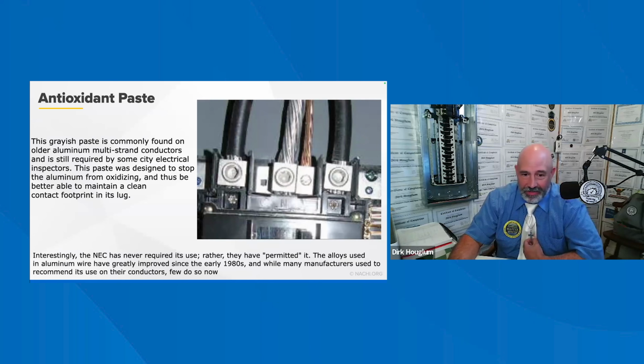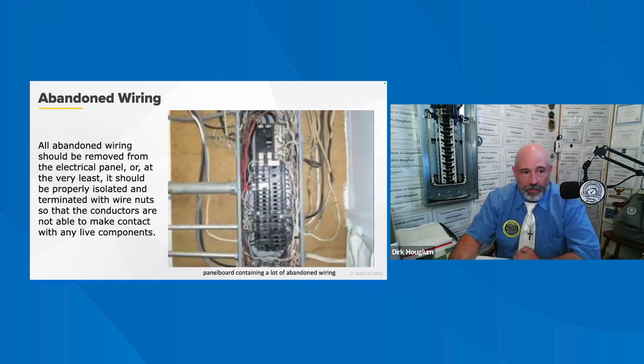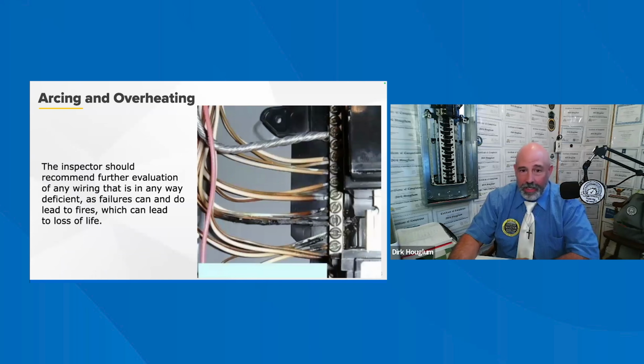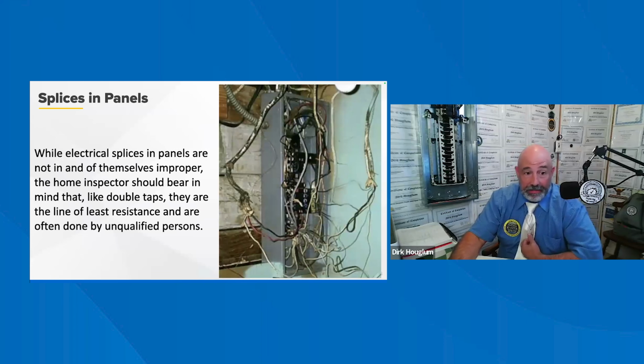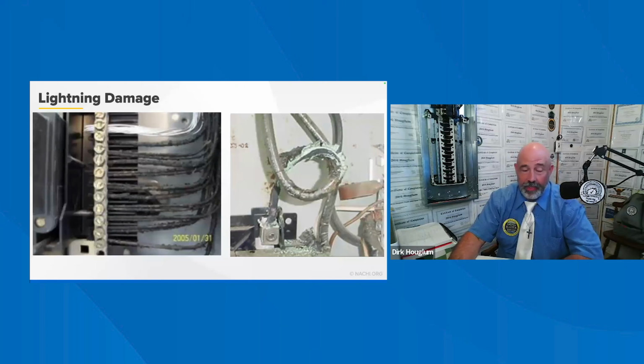Since the 1980s. Anyways, all abandoned wires should be removed. So anytime I see any wire in there, I just make a note of it for further evaluation from an electrician. It's that simple. I've seen this happen too, where the neutral has been burnt up. And there's our timer. And then I've also seen stuff like this. Double taps, just untidy. It has to be tidy. That is part of the NEC. Wires should be nice and neat.